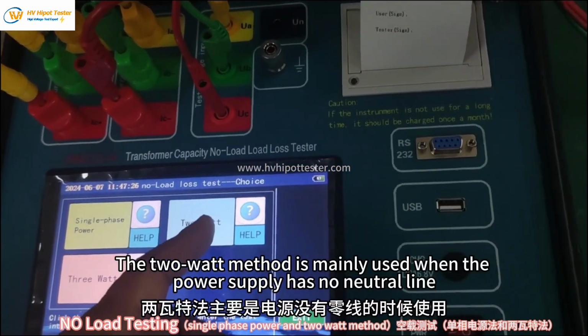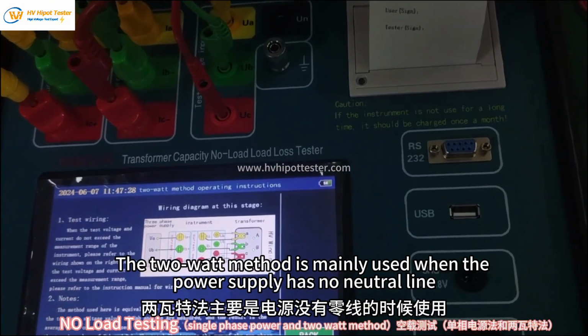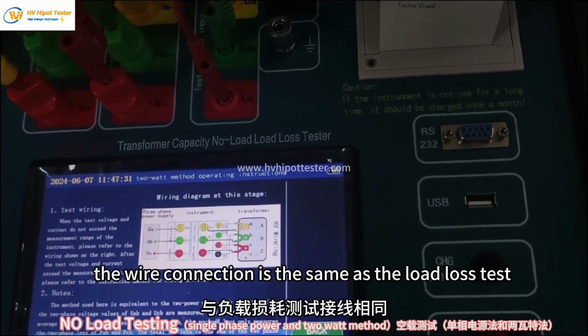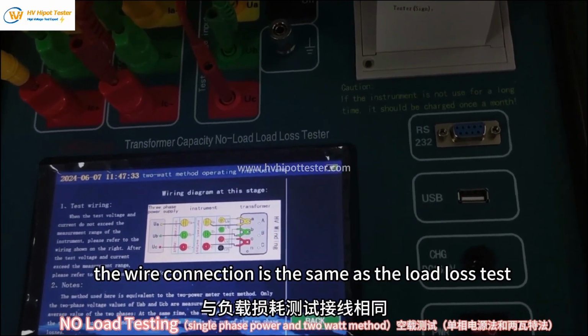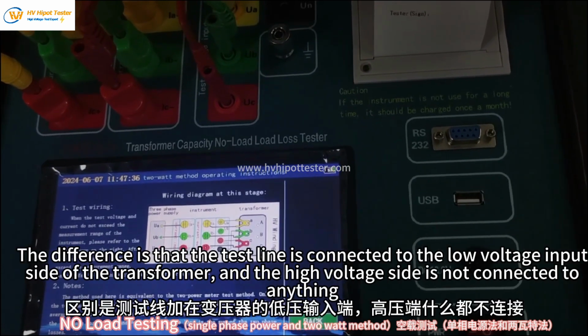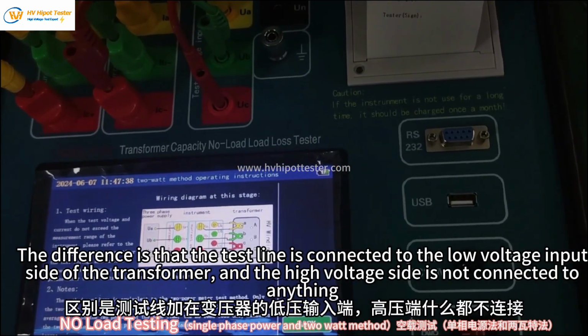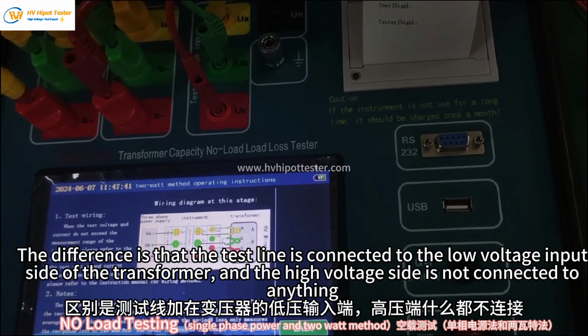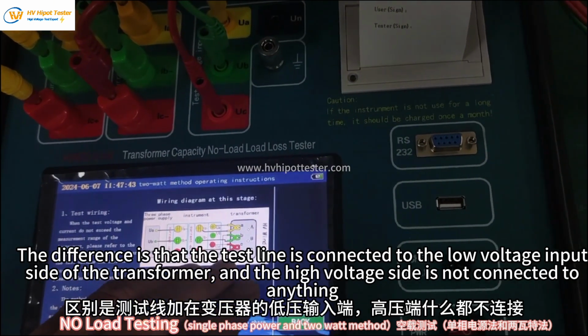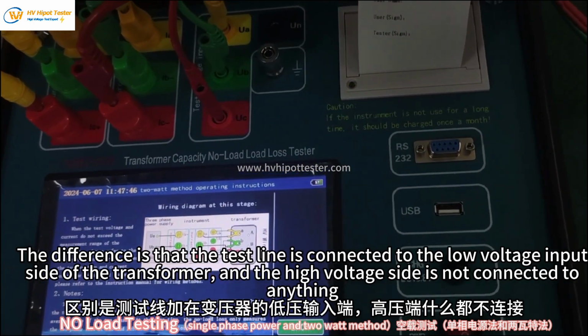The 2-watt method is mainly used when the power supply has no neutral line. The wire connection is the same as the load loss test. The difference is that the test line is connected to the low voltage input side of the transformer and the high voltage side is not connected to anything.